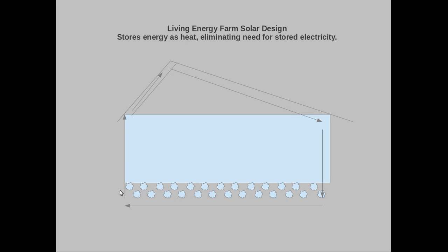So this is a radiant floor system similar to the fluid-based radiant floor systems, except in this case the heat transfer medium is air. This is also made possible because the availability and cheapness of photovoltaic power has come down quite a bit, so it's now a lot more feasible. You have to have a much bigger motor to move heat with air than you do with fluid because of the density, because fluid is so dense it will transfer heat very effectively.